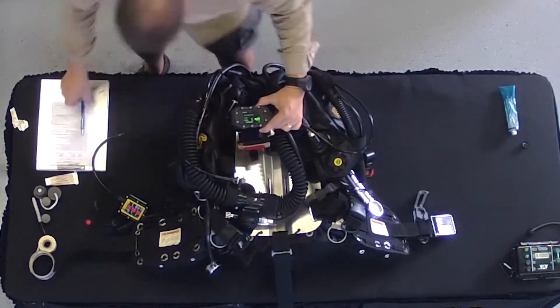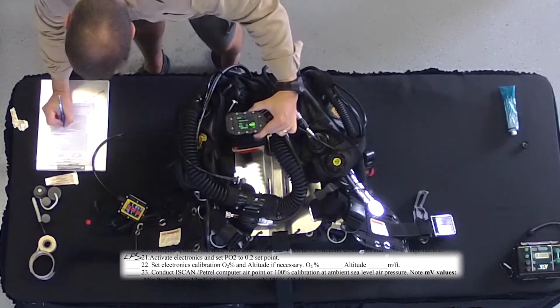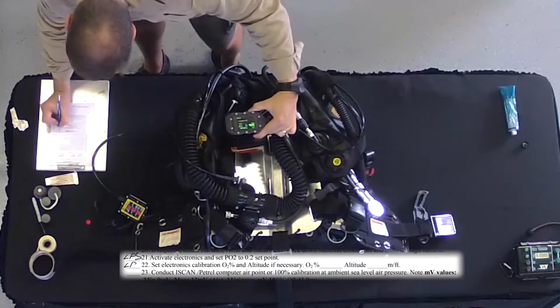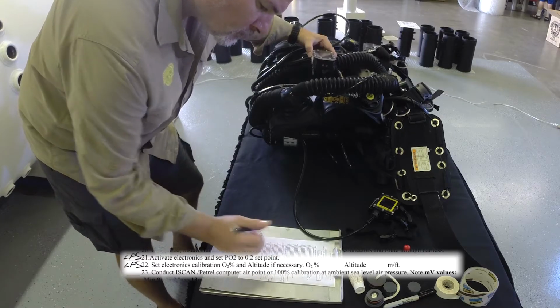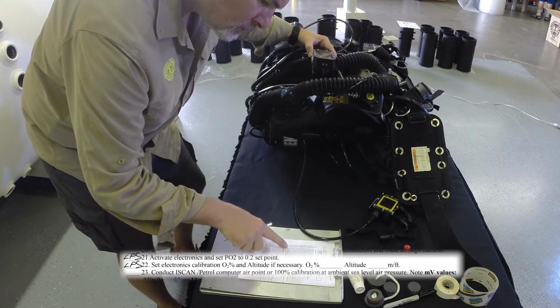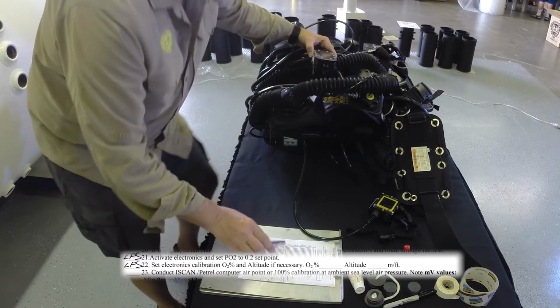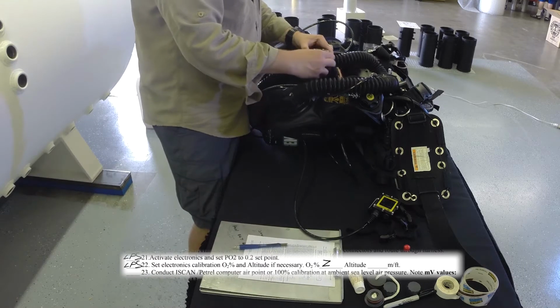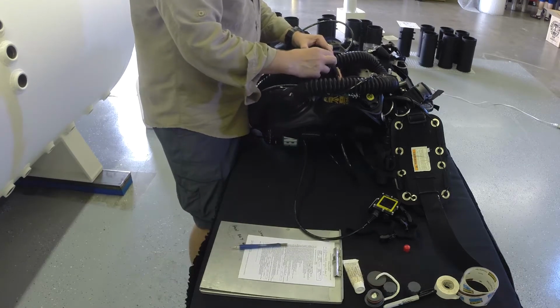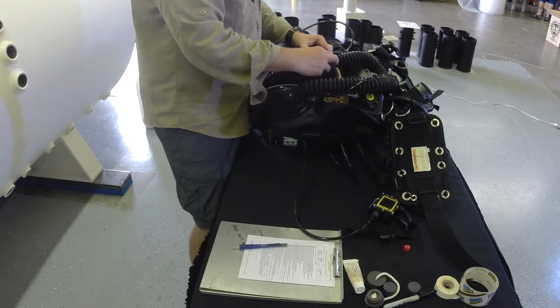Number 22, set electronics calibration, O2% and altitude if necessary. So I'm checking the handset, and the O2% is going to be 21 because I'm calibrating to that. My altitude will be 0 feet or 0 meters. I've checked those.